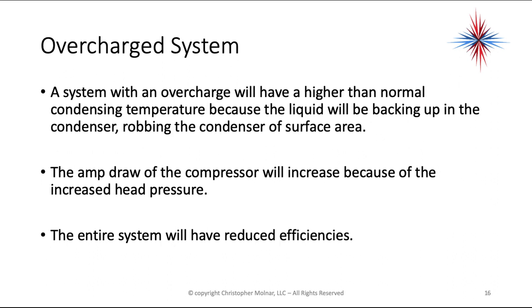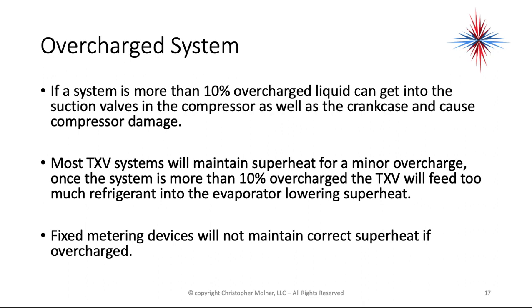An overcharged system has significant differences. A system with an overcharge will have a higher than normal condensing temperature because liquid will be backing up into the condenser, robbing it of surface area. The amp draw of the compressor will increase because of the increased head pressure, and the entire system will have reduced efficiencies. If a system is more than 10% overcharged, liquid can get into the suction valves and crankcase causing compressor damage. Most TXV systems will attempt to maintain superheat for a minor overcharge, but once more than 10% overcharged, the TXV will feed too much refrigerant into the evaporator, lowering superheat. Fixed metering devices will not maintain correct superheats if overcharged.